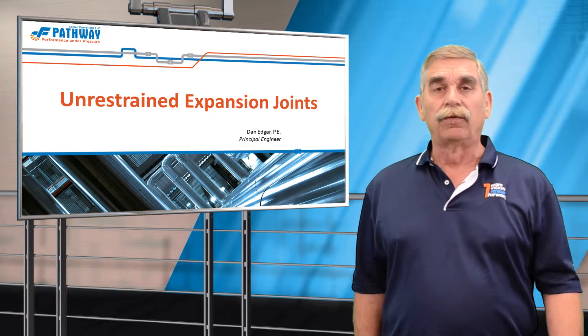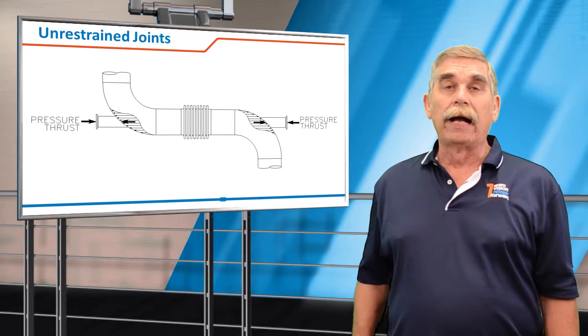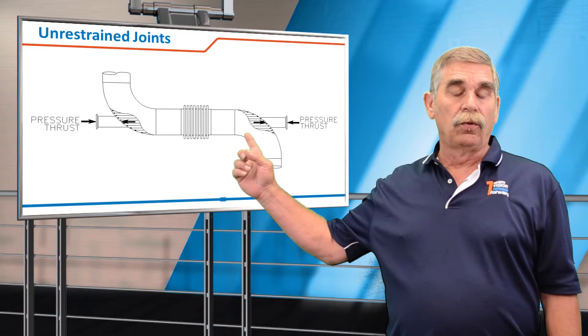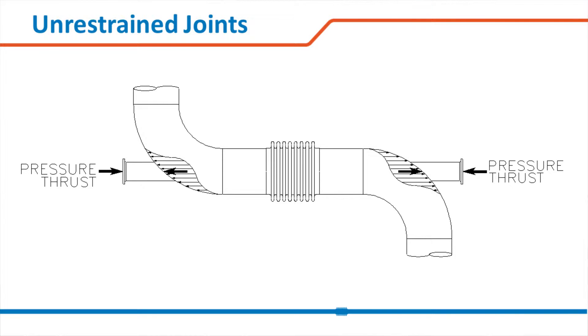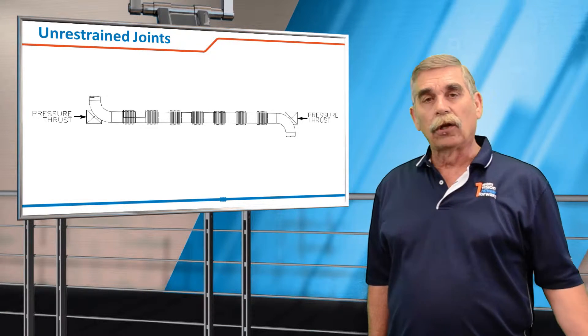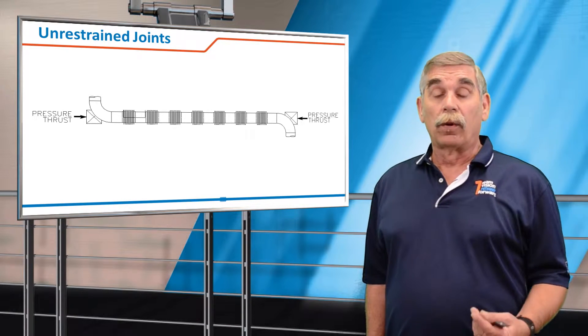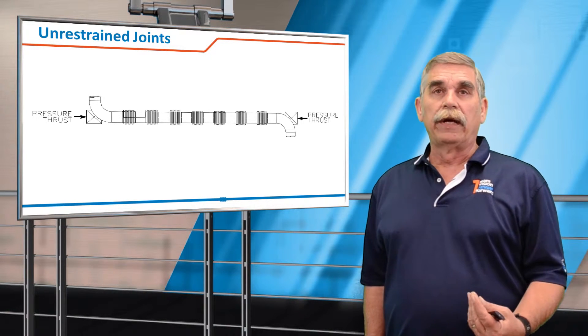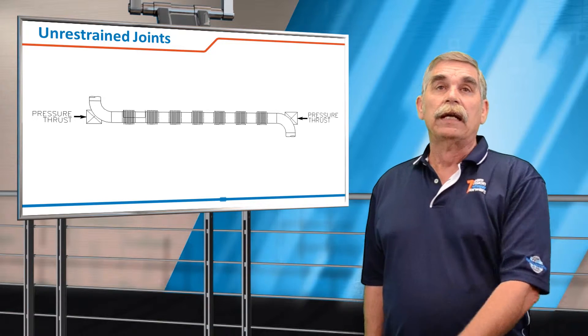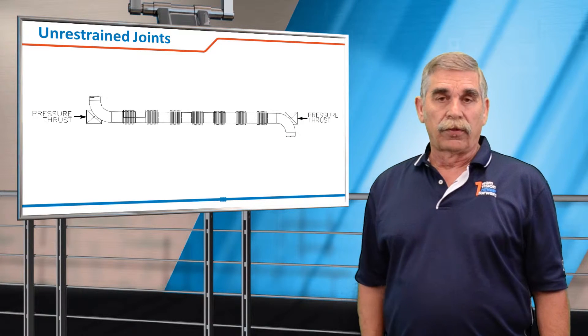Normally they're relegated to low pressure flue gas or off gas systems. In the example we have here, you see where a high pressure system is being restrained by two thrust anchors that take that longitudinal force. They're not used a whole lot, but one good example of how to use them is in very long runs — say a steam distribution line, an LNG loading dock, or a flare line application — where we can use unrestrained joints and stack off the number of joints needed to absorb the thermal growth.